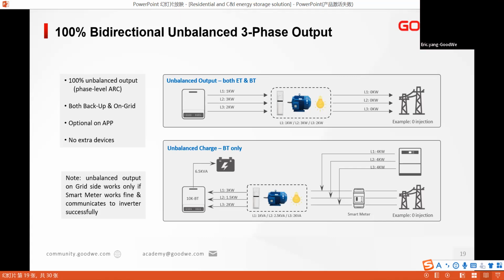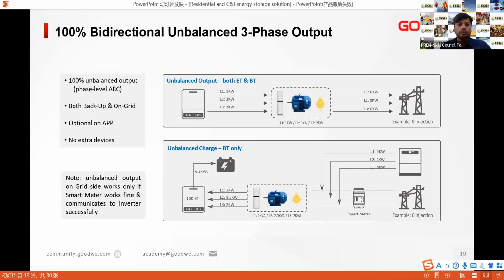If the load consumption is beyond the inverter's maximum output, the other power will be supported from the grid. So if there is no grid, the GoodWe storage inverter cannot support the backup load if it is more than 3.3 kilowatts for a 10 kilowatt inverter.